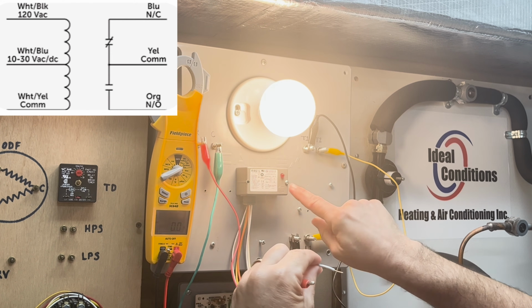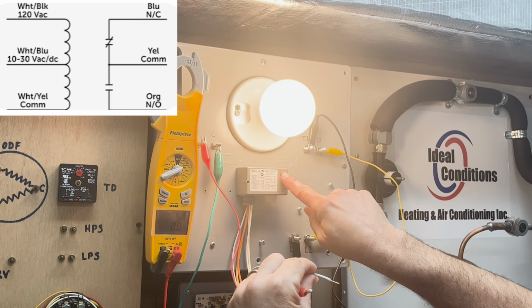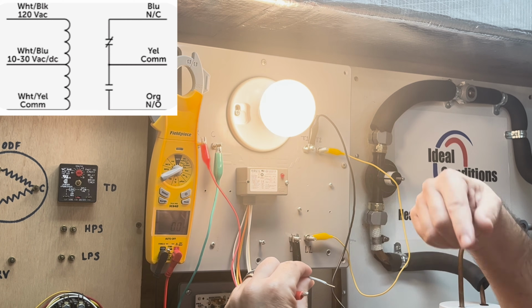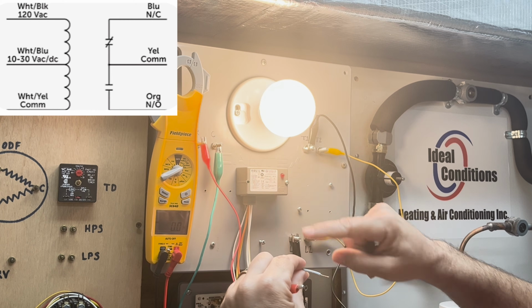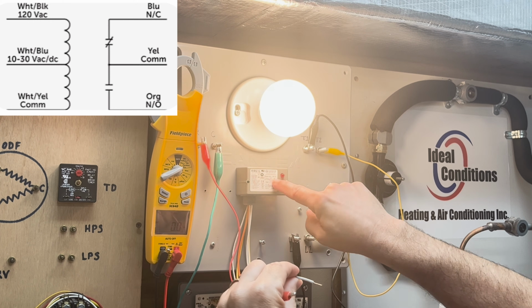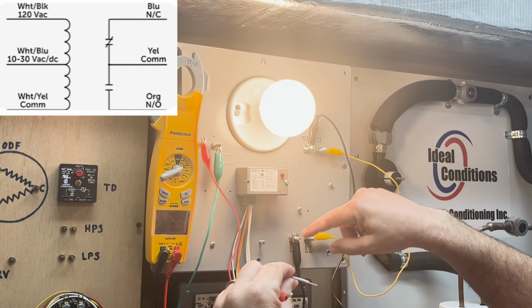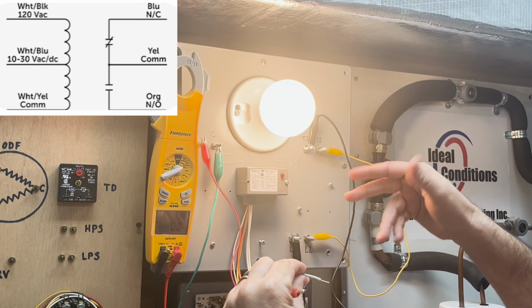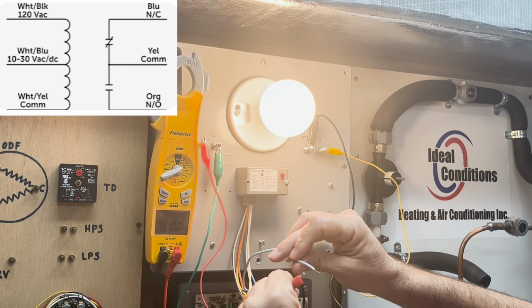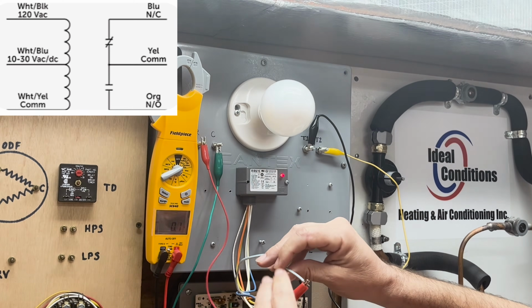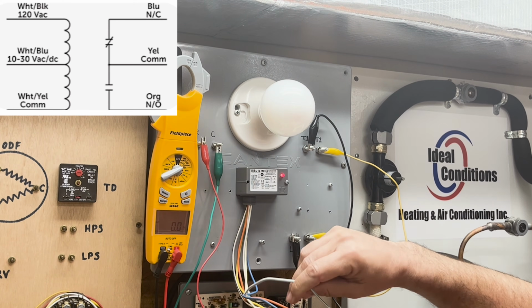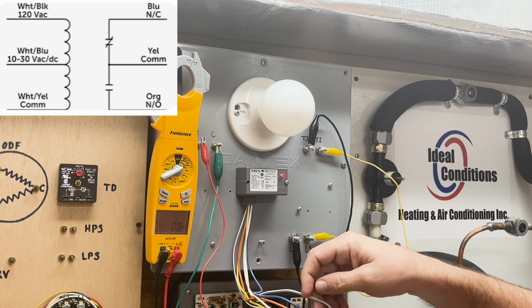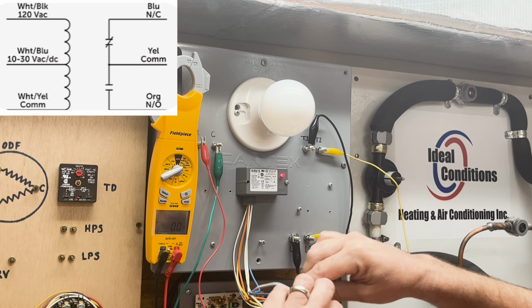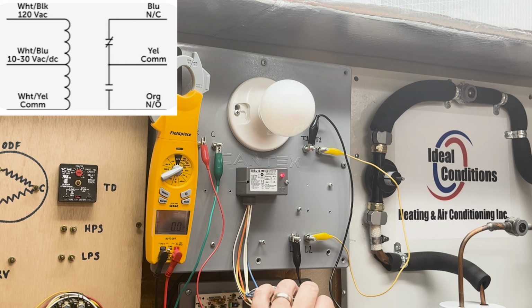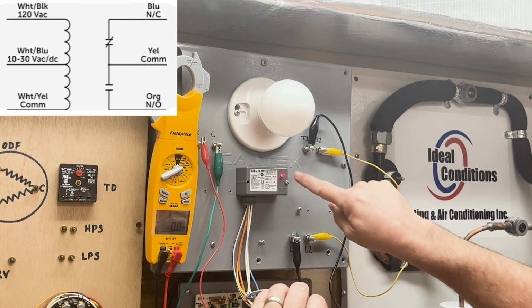You'll notice that a red light will appear on this RIB relay. That's telling us that we have coil voltage. Obviously, once I apply that voltage, our normally closed terminal will open up and the load will shut off. So let's go ahead and do that. And you see we have the light that came on the RIB relay. I'm going to hold these because all these are just kind of floating here and I don't want anything to touch anything, so I'm going to be careful with that. And the light came on.